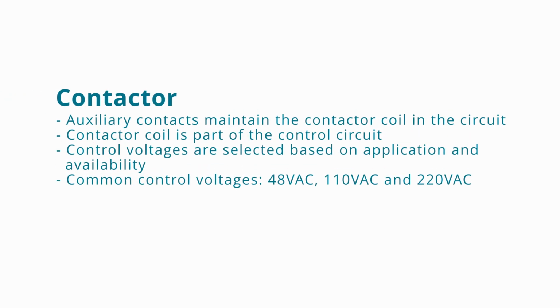The normally open auxiliary contacts are also called auxiliary hold-in contacts, as they hold the contactor coil in place. The contactor coil is part of the control circuit. Contactor coil voltages or control voltages are selected based on application and availability of voltages. Common coil voltages include 48 volts AC, 110 volts AC, or 220 volts AC.